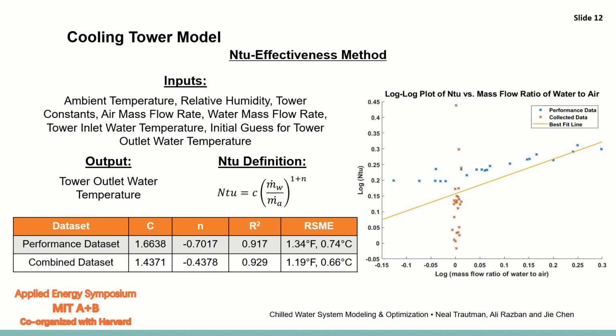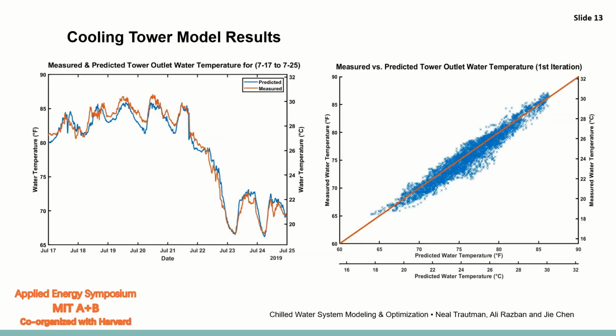The results for our final cooling tower model can be seen in this slide. As you can see, the predicted outlet water temperature follows the measured outlet water temperature fairly well. The measured versus predicted tower outlet water temperature follows good correlation with low root mean squared errors.